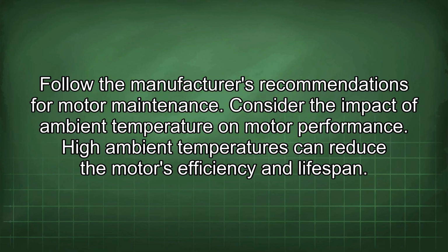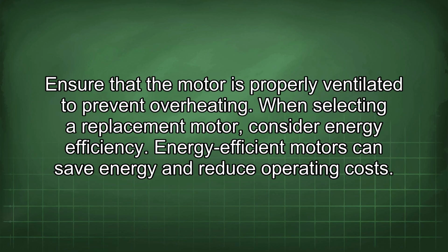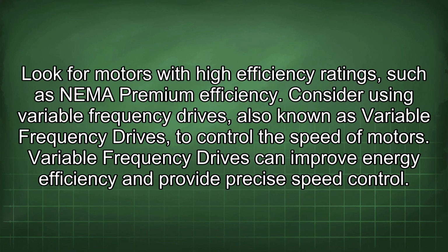Consider the impact of ambient temperature on motor performance. High ambient temperatures can reduce the motor's efficiency and lifespan. Ensure that the motor is properly ventilated to prevent overheating. When selecting a replacement motor, consider energy efficiency. Energy-efficient motors can save energy and reduce operating costs. Look for motors with high efficiency ratings, such as premium efficiency.